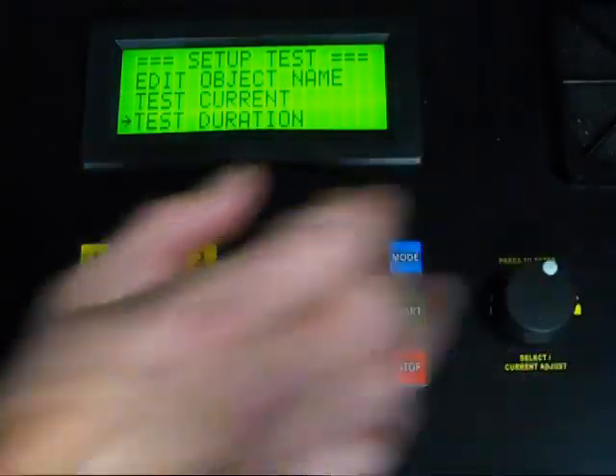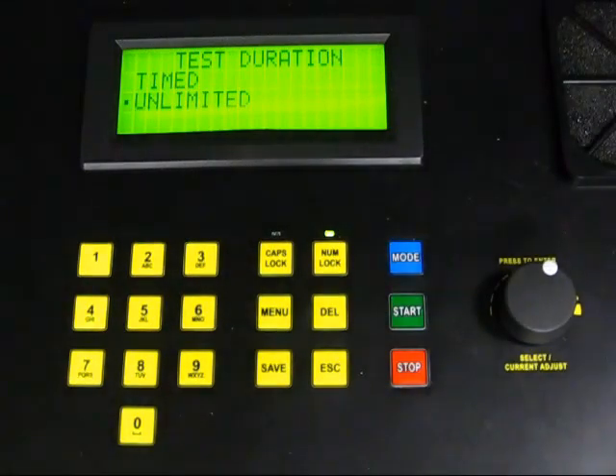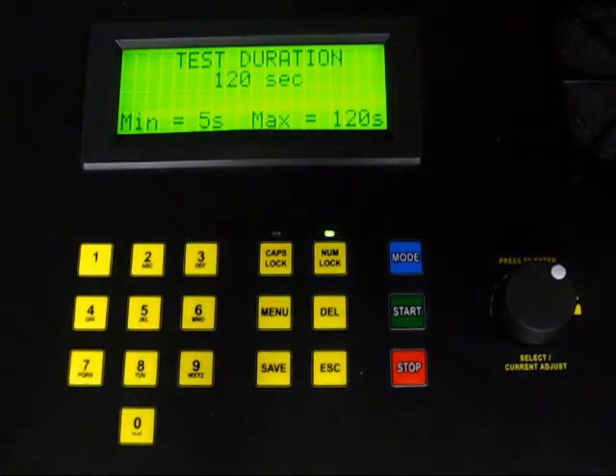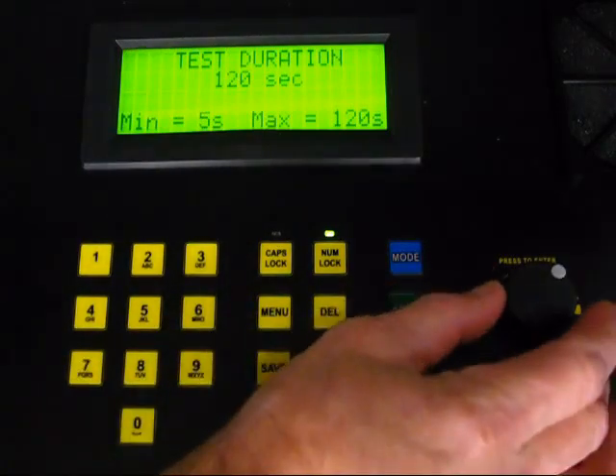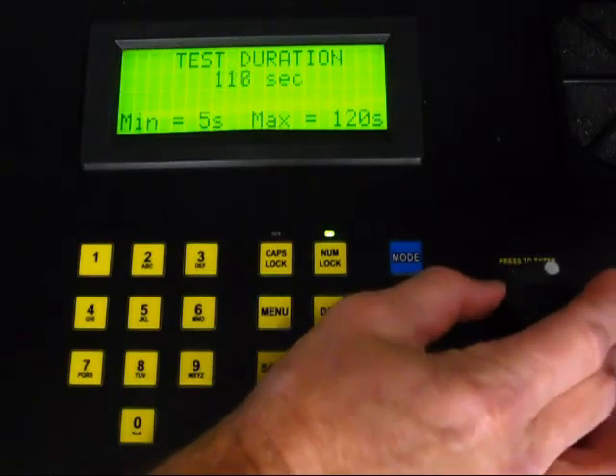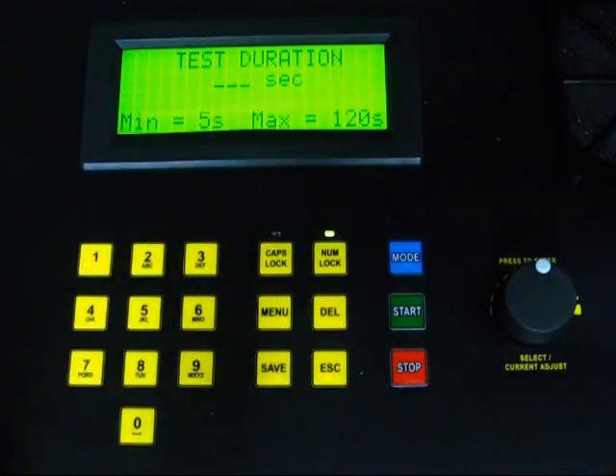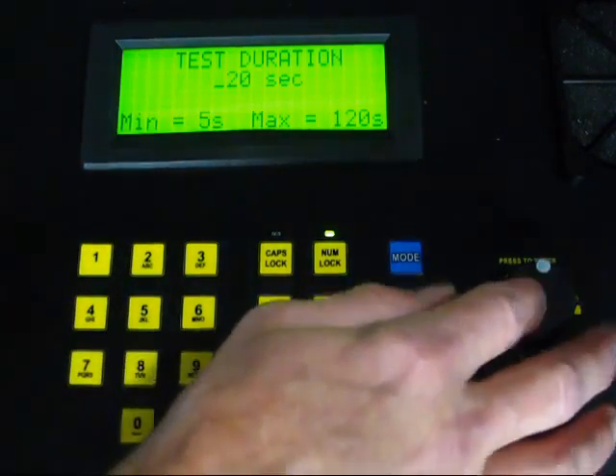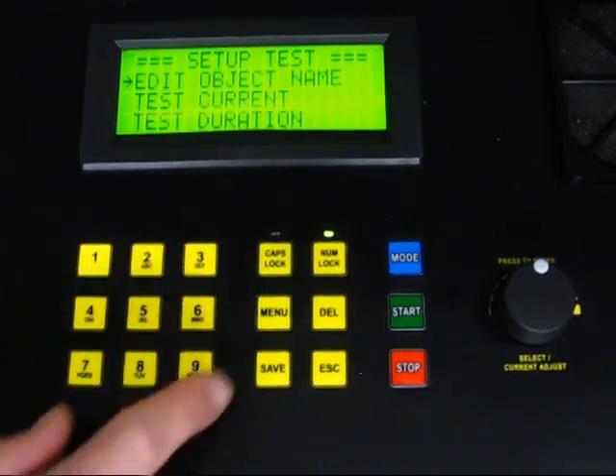We now choose Test Duration to select the length of the test. There are two options: Timed and Unlimited. Unlimited is for an untimed test — the test will run continuously until you press the Stop button. We want to set the test duration, so we select Timed. There are two ways you can enter the duration: one is by using the keypad to type in the number of seconds, and you can also turn the rotary knob to select a higher or lower number. For timed tests, the minimum duration is 5 seconds and the maximum is 120 seconds. In our demonstration, we will select 20 seconds. After setting the duration, you must press the rotary knob to save the setting and return to the Setup Test menu.